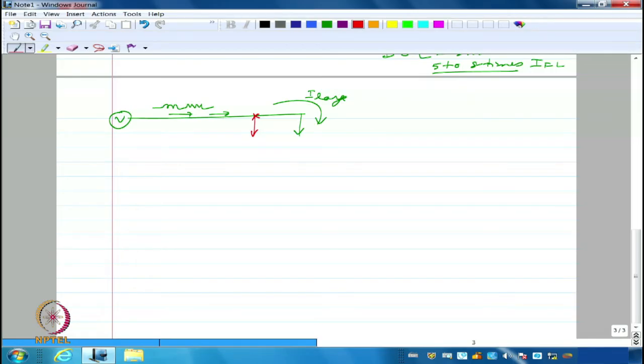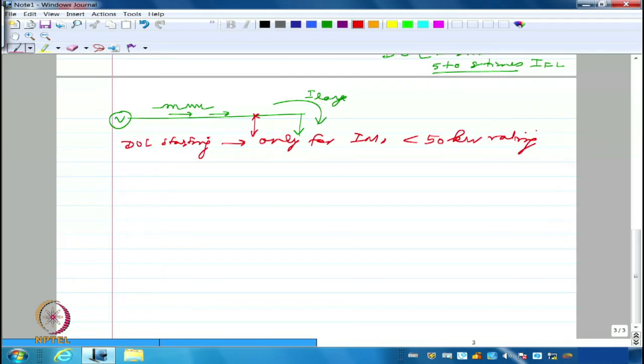That's it. So DOL starting normally is used only for motors less than strictly 50 kilowatt rating. In fact, even for 10 kilowatt rating, maybe until 10 kilowatt rating, it is okay to use it. But definitely not for greater than 50 kilowatt rating, right? So I should have some other method of starting the machine. So another method of starting which is very commonly used is star delta starting.